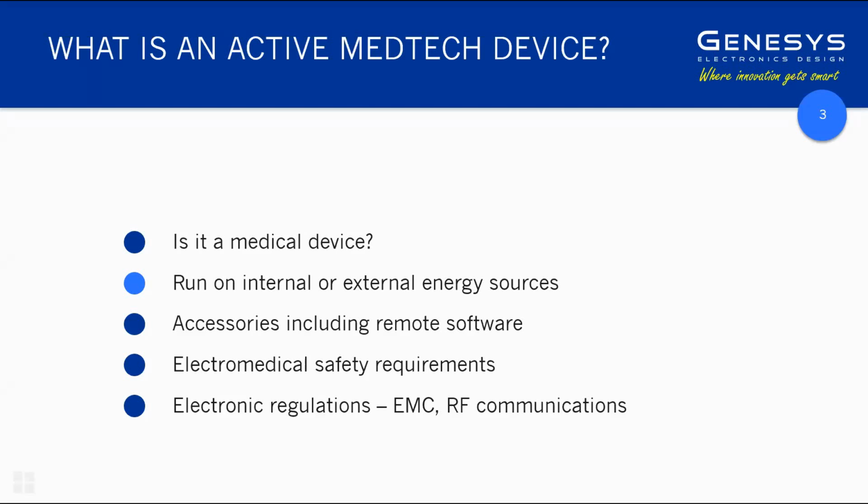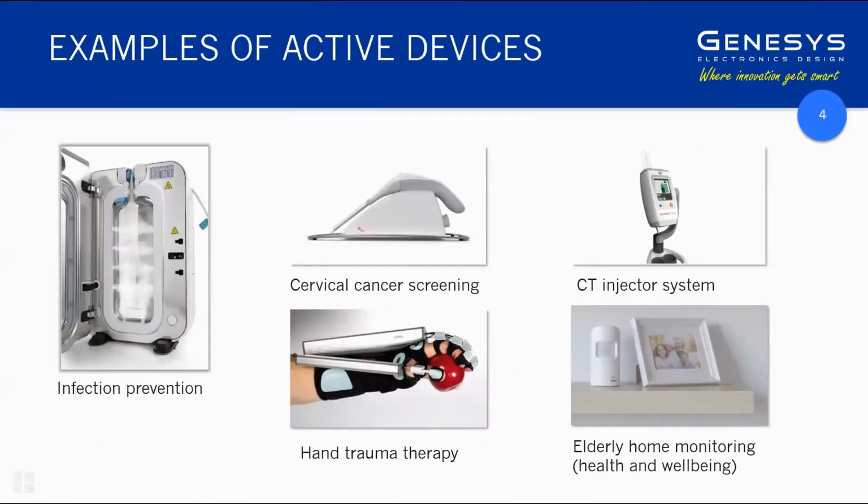I think Tim's covered the headline issues pretty well in terms of an active medtech device, but I will make the comment, and I will expand on this shortly, that whether a device is a medical device or not very much depends on what it's used for. So you can have devices that may be a medical device in some uses, and the very same device may not be considered a medical device in other cases. It's important to draw this distinction.